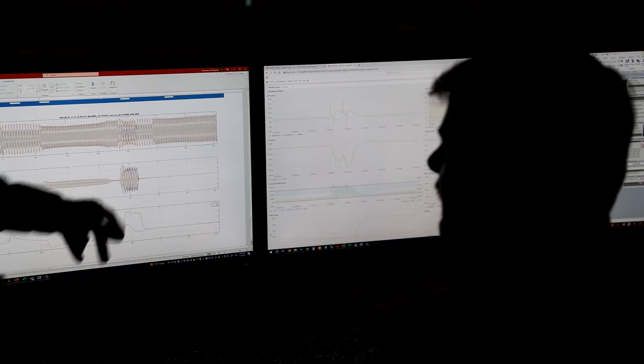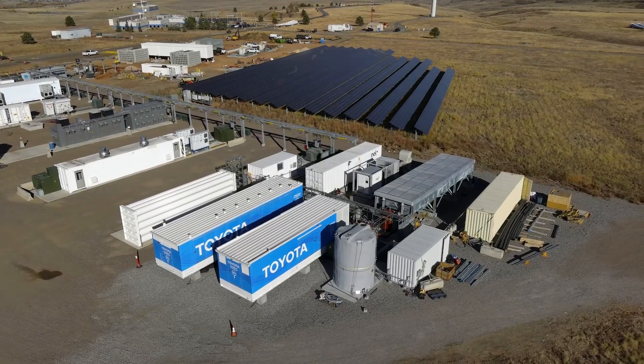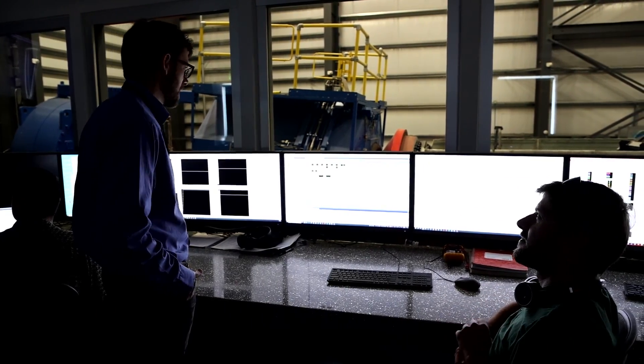We proposed three different ways of mitigating those oscillations. We then took those and actually tested them in our lab, where we have an actual megawatt-scale hardware inverter — the same as one of the inverters out on that island — connected it up to a model of the Kauai power system.